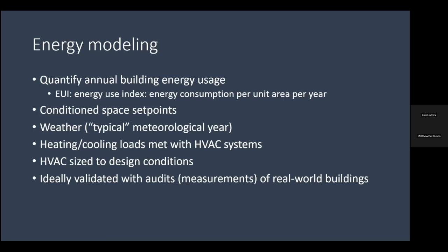We meet heating and cooling loads with HVAC systems, which is one of the drivers of energy use. In the models, we size the HVAC according to design conditions. Basically you look at the worst case weather situation and take some percentage of that, maybe 95% or 97%. That means your HVAC system is sized to meet the loads 97% of the time. They do that because if you size the HVAC to meet the absolute worst case, it might be a very expensive system you're not going to need most of the time.